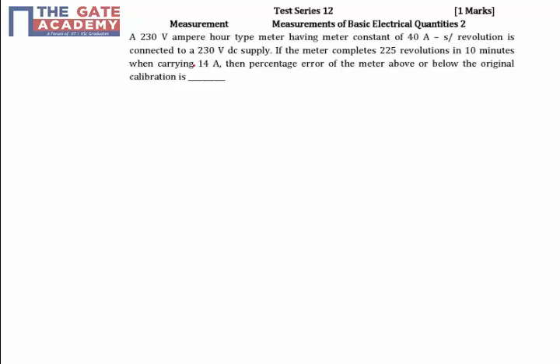In the given problem, a 230 volt ampere-hour meter with a meter constant of 40 amperes-second per revolution is connected to a 230 volt DC supply. If the meter completes 225 revolutions in 10 minutes when carrying 14 amperes, we need to find the percentage error of this meter. First, we calculate what the meter is recording.